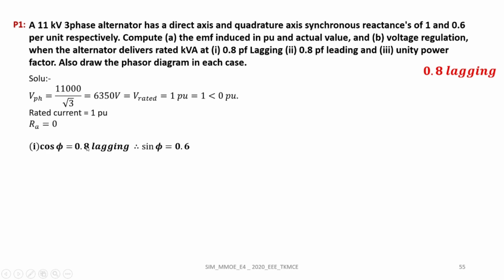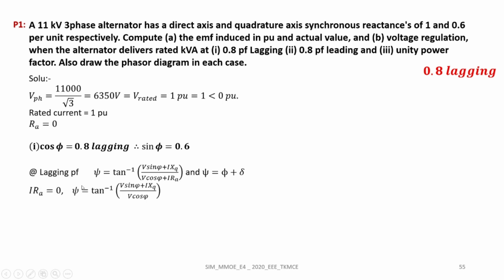We know corresponding to lagging power factor, here the power factor is 0.8, therefore sin phi is equal to 0.6. So corresponding to lagging power factor, the internal power factor angle equation is psi equals tan inverse of (V sin phi plus I Xq) divided by (V cos phi plus I Ra), and the relationship between the angles is psi equals phi plus delta. As armature resistance is 0, this simplifies to tan inverse of (V sin phi plus I Xq) divided by V cos phi. Substituting the per unit values of voltage and current as 1 per unit, sin phi equal to 0.6, Xq is 0.6, Xd is 1. So substituting all these values, psi is obtained as 56.3 degree.